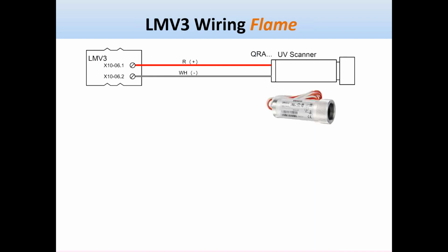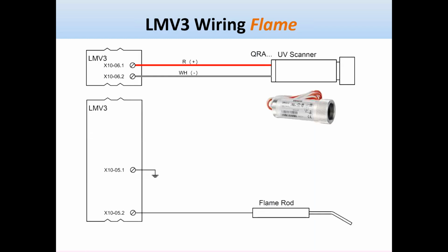As far as the flame scanners on the LMV3, the most common use would be a QRA4, and there would be 2 wires going to X1006, and that would be a UV scanner. This would not be self-check. This would be a UV scanner to the LMV3. And the LMV3 additionally could take a flame rod in lieu of the UV scanner. Flame rods are inexpensive inputs. Every flame safeguard that I've ever seen has a flame rod input. It's a very simple input.